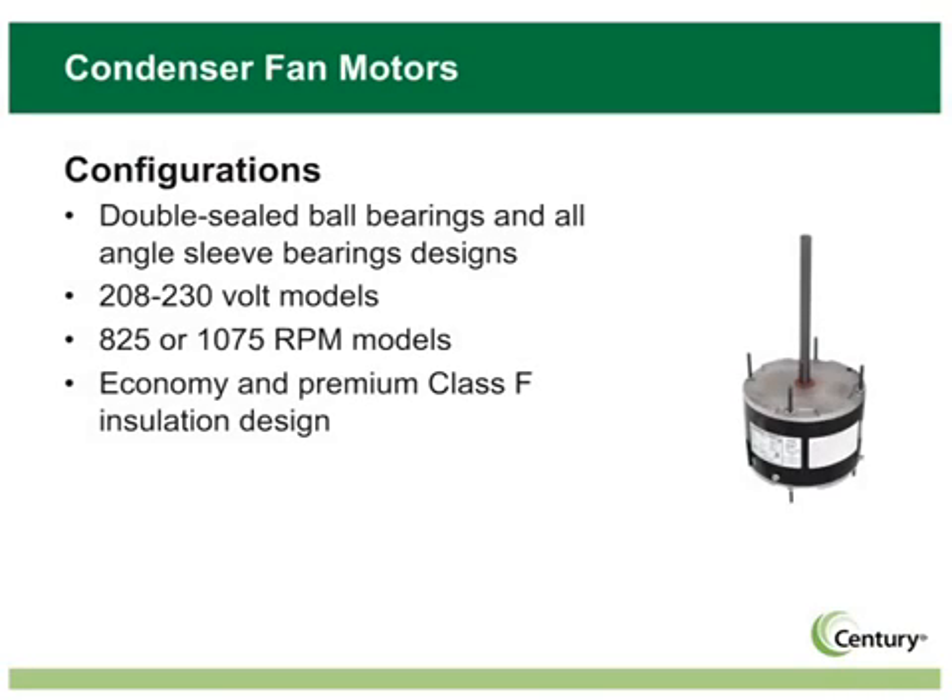MasterFit Pro reduces your condenser fan motor needs to just five models. These motors are 208 to 230 volt, and are designed with Class F insulation, so you have all the benefits of a 70 degree Celsius ambient rating. The vast majority of condenser fan motors on the market are only rated for 60 degrees. The higher Class F insulation ratings of MasterFit Pro can mean longer life and fewer overload nuisance trips, which means fewer callbacks for the busy contractor. These motors also feature ream mounting screws in the shell, and have the additional taps in the end bells for the off-standard trane and ream mounts.